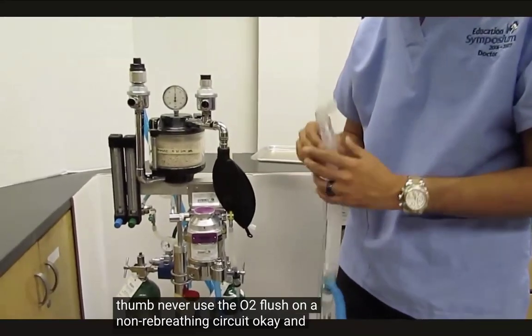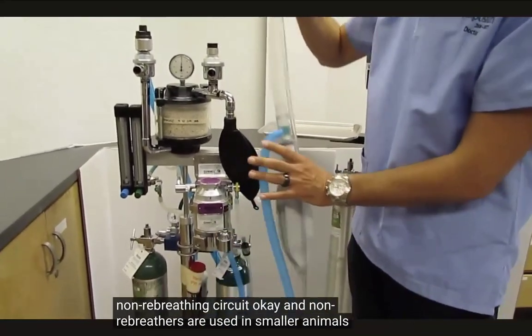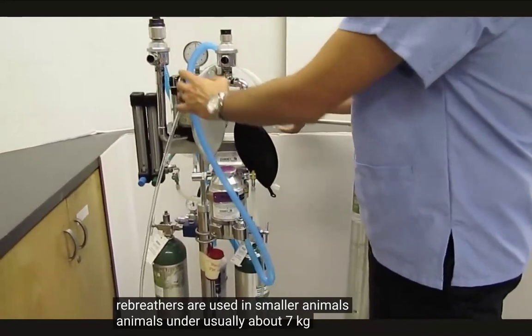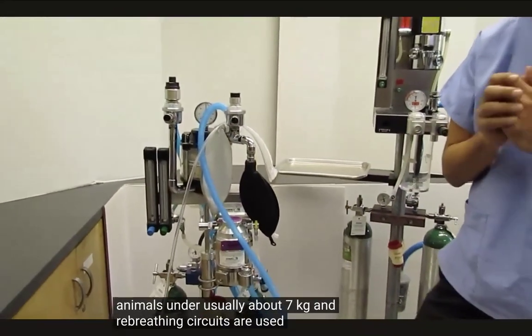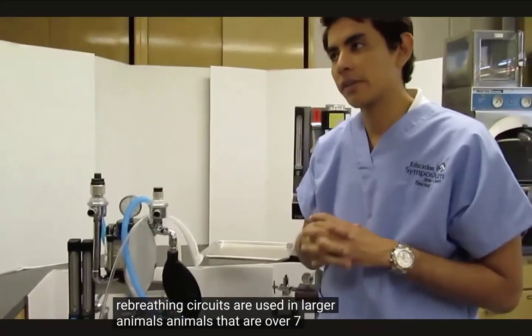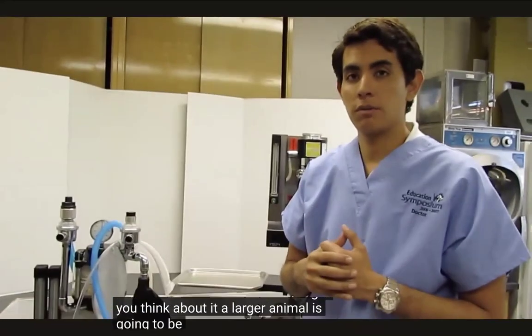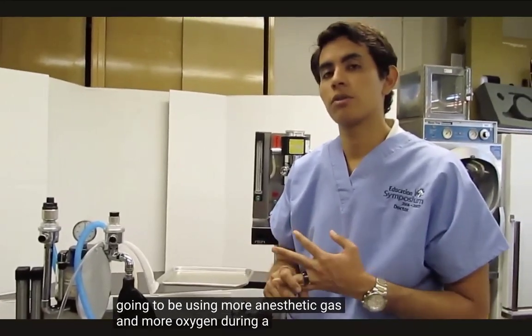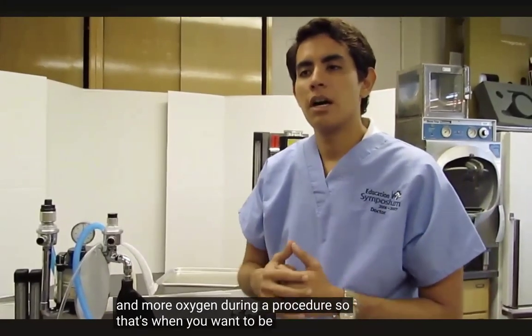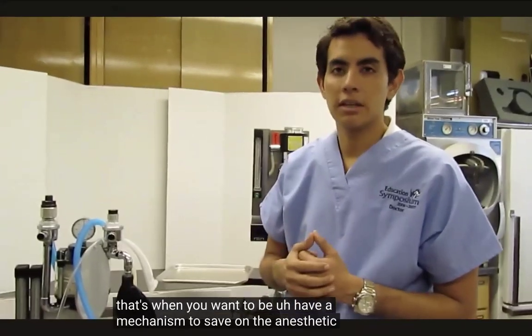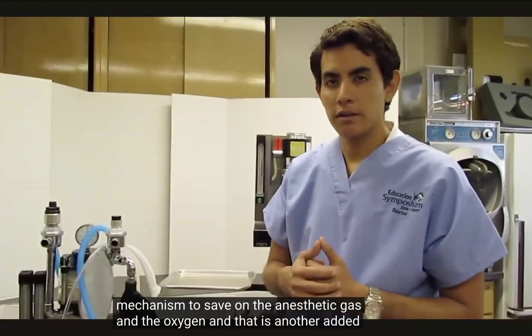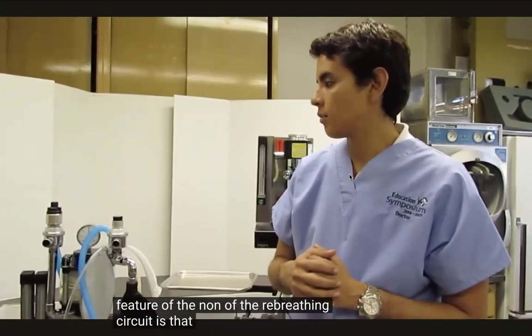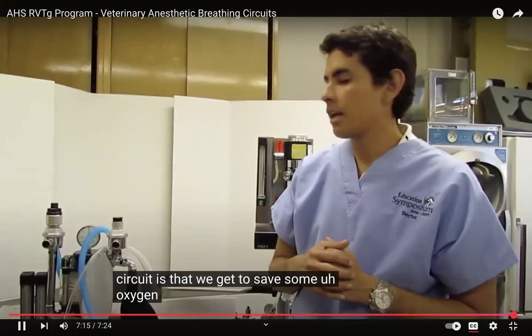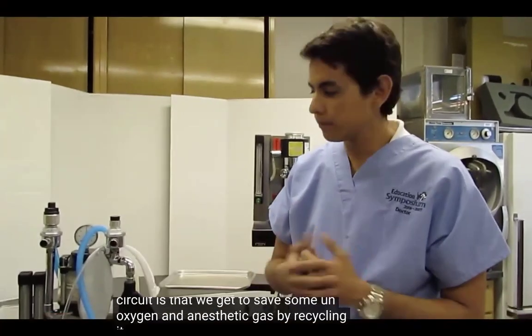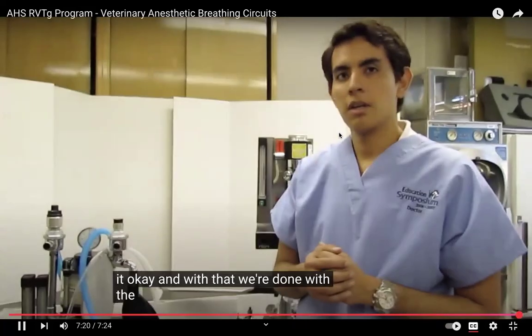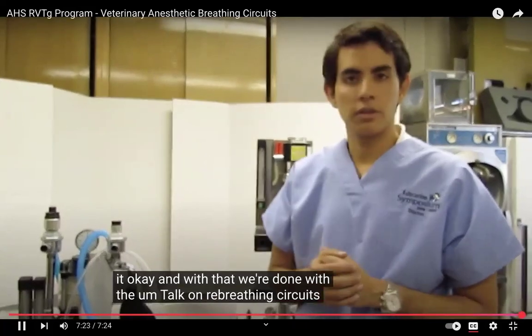Okay? And non-rebreathers are usually used in smaller animals under about 7 kilograms, and rebreathing circuits are used in larger animals that are over 7 kilograms. If you think about it, a larger animal is going to be using more anesthetic gas and more oxygen during a procedure, so that's when you want to have a mechanism to save on the anesthetic gas and the oxygen. That is another added feature of the rebreathing circuit, that we get to save some oxygen and anesthetic gas by recycling it. Okay, and with that, we're done with the talk on rebreathing circuits.